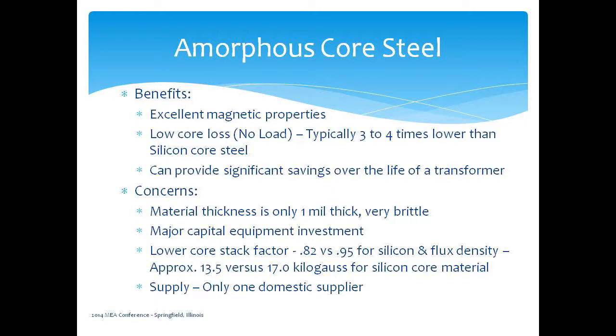One of the biggest things everyone looks at is the stack factor. On silicon steel, you're looking at flux density of the core and how one layer stacks on top of another - for silicon steel it's right at 0.95, so when you stack it layer by layer there's a 0.05 air gap between them. If you look at amorphous steel, because you don't roll it on both sides - it's only flat on one side - there's more air gap between it. But when you're talking about the super efficiency of amorphous versus the highest grade of M2, the amorphous wins hands down - it's just very, very efficient.